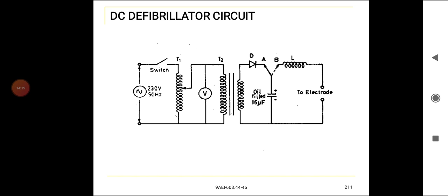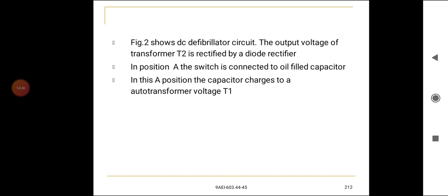The figure shows a defibrillator circuit. The output voltage of transformer T2 is rectified by a diode rectifier. In position A, the switch is connected to the oil-filled capacitor. In this A position, the capacitor charges to the auto transformer voltage of T1. During delivery of shock to the patient, the switch is changed to position B and the capacitor C is discharged across the arc. An inductor L is placed in one of the electrode leads so that the discharge from the capacitor is slowed down by the induced counter voltage. The success of defibrillation depends upon the energy stored in the capacitor.